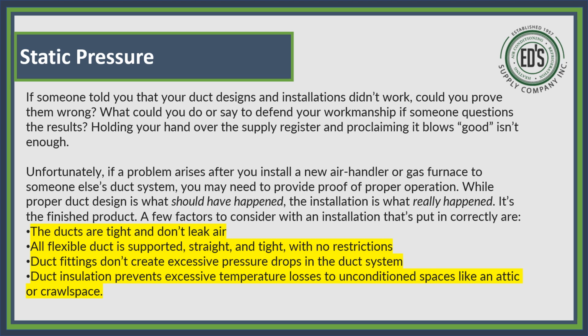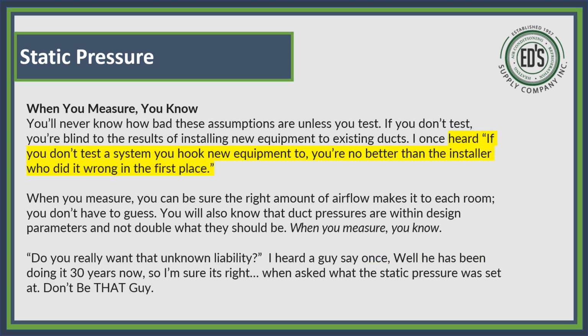and don't leak. All flexible duct is pulled tight, it's straight, and it's supported with no restrictions and no kinks. Duct fittings don't create excessive pressure drops in the duct system. Don't put in a system with a square throat, square back without any turning vanes. Use round pipes or round throats or round heels. Duct insulation prevents excessive temperature losses to unconditioned space like attics or crawl spaces.